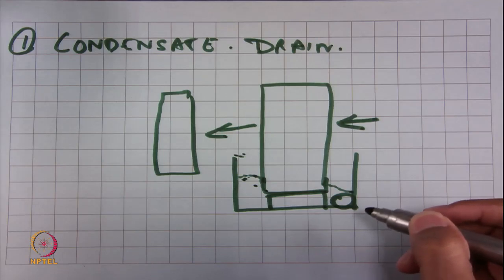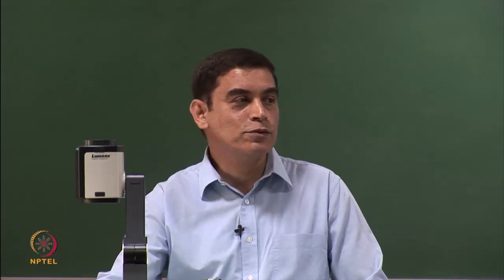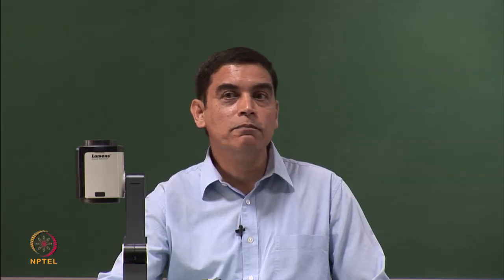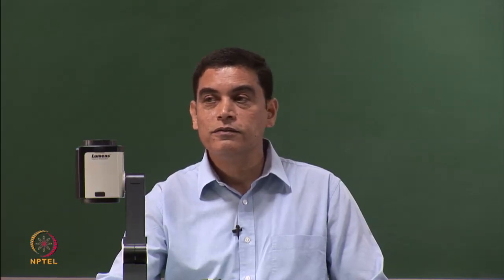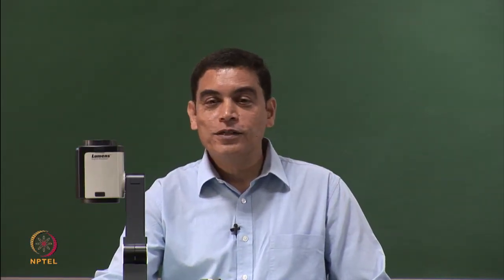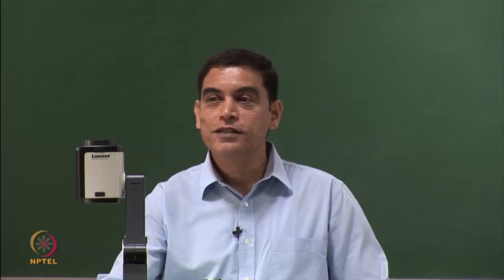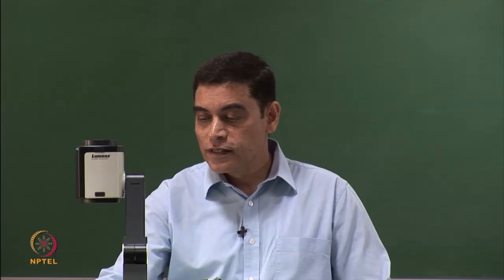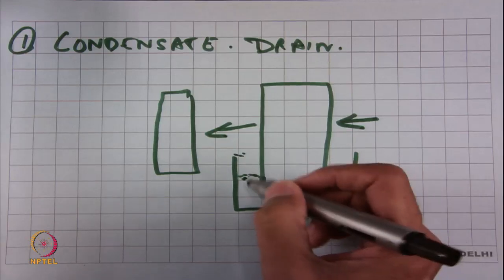This is something we never got from railways as a requirement. We did not know it until we put the unit on a train and it went a couple of times to Bombay, and then passengers complained that water was being thrown in. Our first guess was that Bombay is humid, there is rain, and therefore it is rainwater from the trough. So we went, and it was rainy, and we found that there was water from the trough which could also spill in, and that was another thing that railways had to take care of. But we also found that this was a concern area.